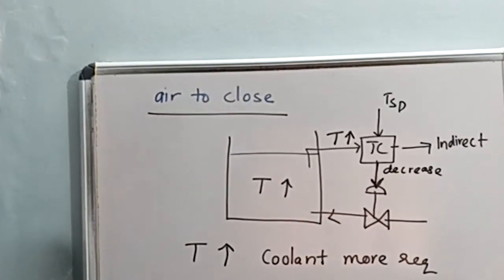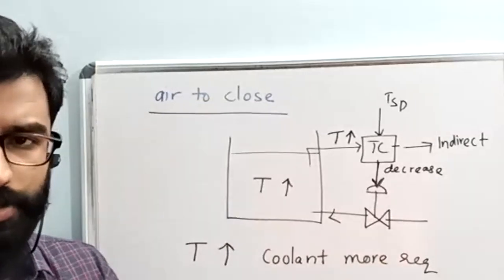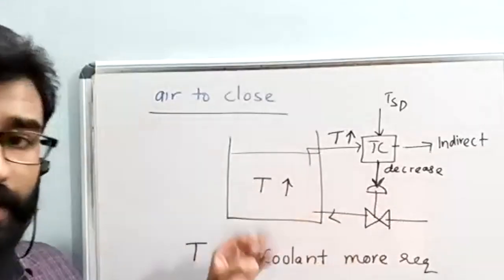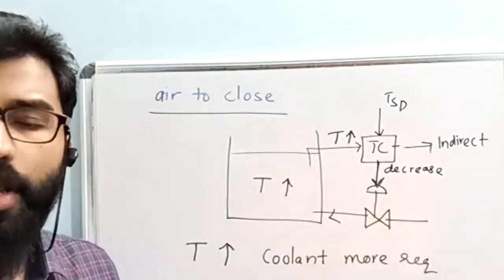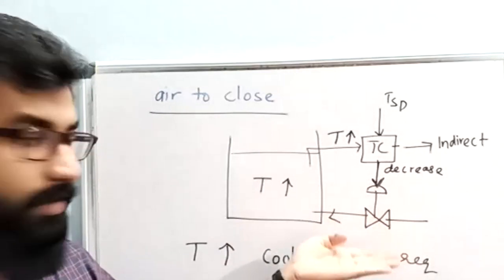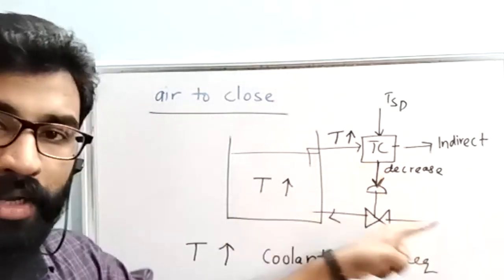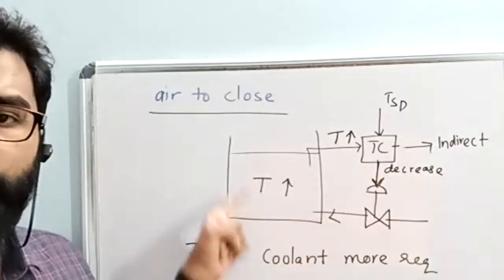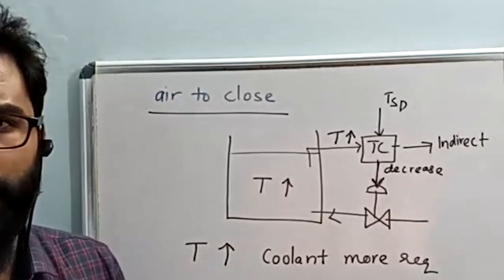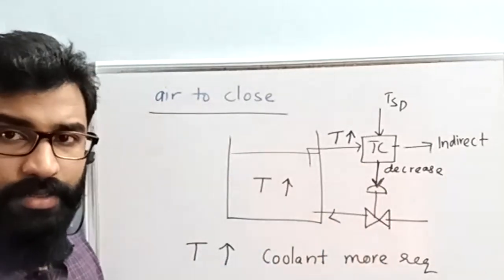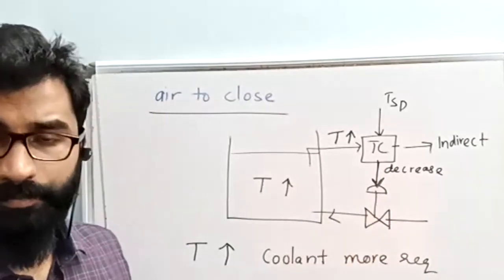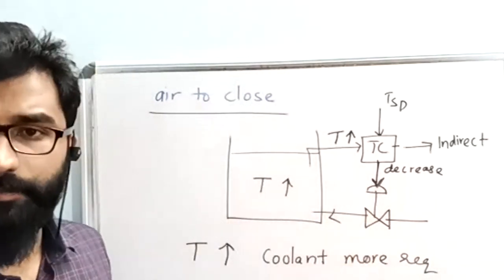Right. So there's one doubt coming in once again: how to identify failure condition? We are not identifying failure condition, right? If it is an exothermic reaction, in case of failure, that is, the valve is not working. If the valve is not working and is closed, no coolant will be flowing inside and that will damage the reactor because the temperature will go up. So if something happens to the valve in the failure condition, the valve should be open, in case of exothermic.